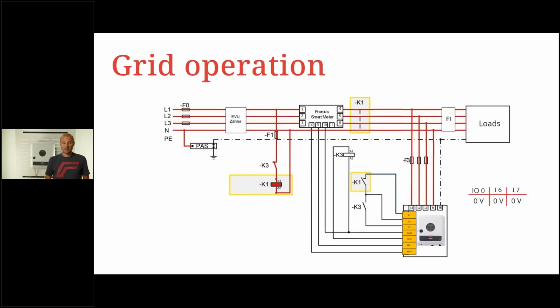How does it work? You see, K1 is here a contactor which is in this position, grid operation on. So it's all grid supplied. The inverter can run in grid mode. Also, all the contactors will be open, and so the feedback signals are open. K1 and K3 auxiliary contacts are open. K1 is supplied from the single first phase 1, via a fuse, 6 amp fuse, and K3 normally closed contact.